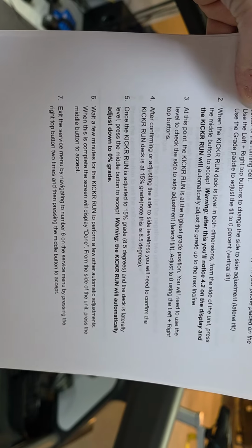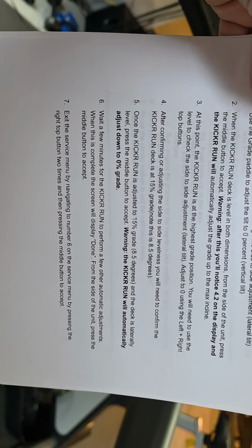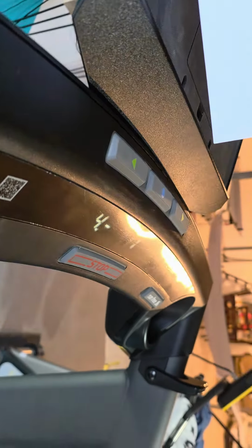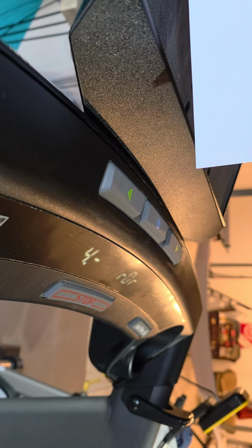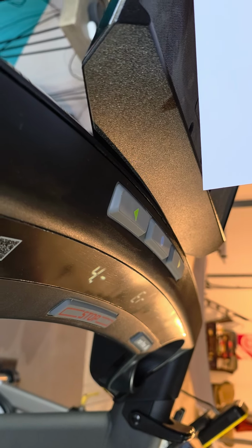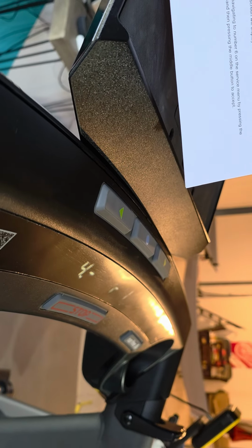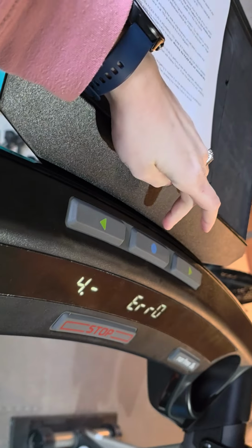So after confirming or adjusting the side-to-side levelness, you need to confirm the KICKR RUN is at 15% gradient or 8.5 degrees. Using my cell phone, it says that I am at, lovely. Perhaps I should have had that in a better spot before I started, but it is all elevated. It looks right. I can't imagine it would need to be higher than that. But if you need me to redo this part, let me know. So once it's adjusted to 15% grade, the deck will laterally level. Press the middle button to accept, and then it's going to adjust down to 0 degrees. So middle button to accept.